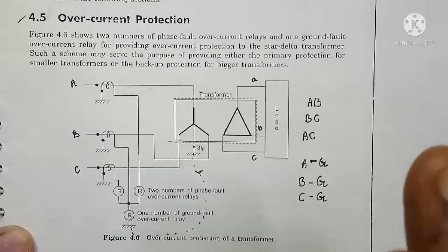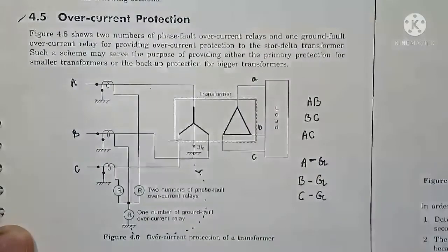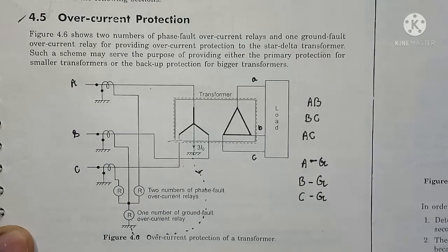Otherwise, the relays will maloperate. In other words, the pickup current of the relay should be more than unbalanced current and harmonic current.